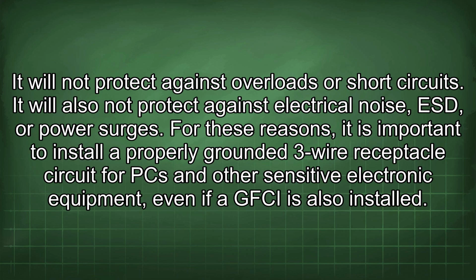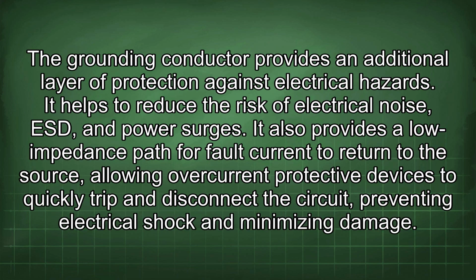For these reasons, it is important to install a properly grounded 3-wire receptacle circuit for PC and other sensitive electronic equipment, even if a GFCI is also installed. The grounding conductor provides an additional layer of protection against electrical hazards. It helps to reduce the risk of electrical noise and power surges. It also provides a low impedance path for fault current to return to the source, allowing overcurrent protective devices to quickly trip and disconnect the circuit, preventing electrical shock and minimizing damage.